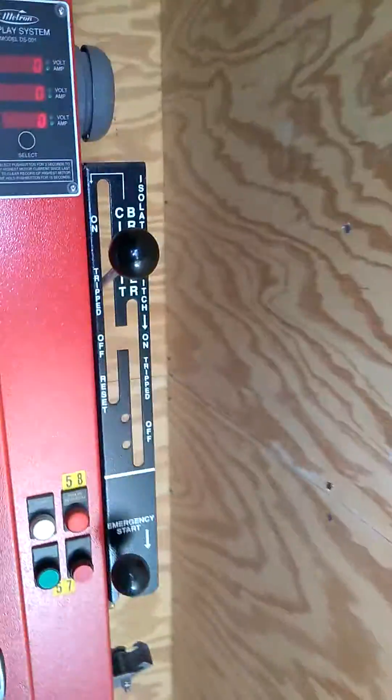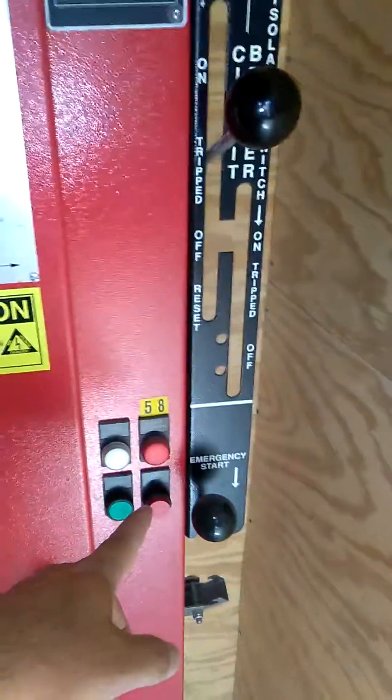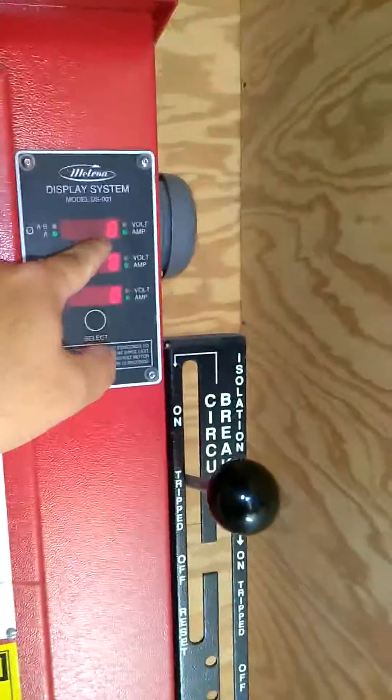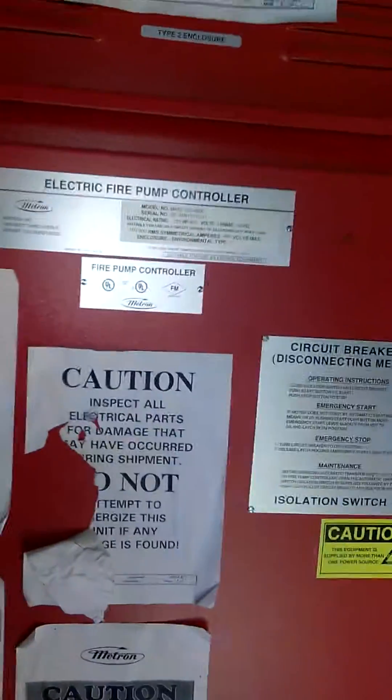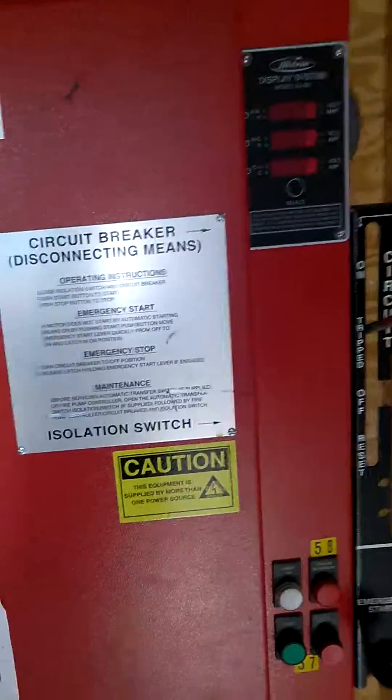What had happened was it had tripped. So I push the stop button, hold the stop button down, go down to reset, and then drive it all the way up to the on position. And then I got 0, 0, 0 volts on there. That's what it's supposed to be whenever it's in normal operation.